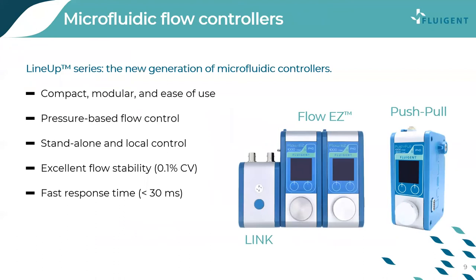Let's focus on one of our flagship technologies — the LineUp series, developed in 2017. We developed this series to fulfill demand for compact and modular flow controllers that could be commanded locally. It consists of a set of modules that can be added or rearranged to meet different experimental designs. The Flow EZ is one flagship module — a standalone compact pressure-based flow controller. You can control pressure using a PC, or without a PC by adjusting the dial, enabling pressure or flow rate control and volume dispense.